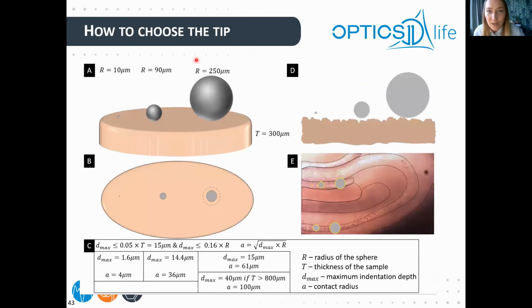Yes. Now, how to choose the tip. You will find the document and the attached information. I will just quickly go over these very important details. So, okay, what you see here, I tried to draw a brain tissue of a thickness of 300 micrometers. And then we have 3 probes, 10 micrometers, 90, and 250 micrometer radius. Now, the first condition, and that all arises from Hertz model assumptions: your indentation depth shouldn't be more than 5% of the sample thickness. Now, the sample is 300 micrometers. That means you cannot indent more than 15 micrometers. The second condition is that the indentation depth should be less than 16% of the tip radius, at least for the standard Hertz parabolic model.